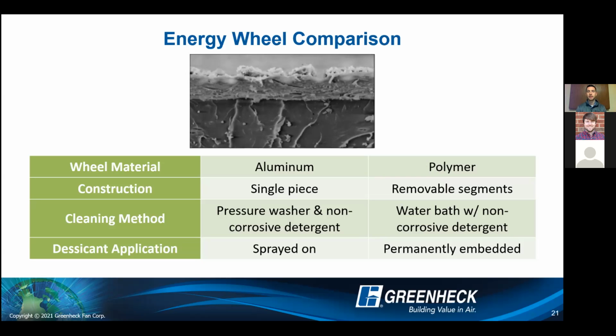So with that aluminum wheel, I talked about the molecular sieve desiccant doing that latent transfer. That is a sprayed on application. So when you're spraying on that desiccant, if you're cleaning it and pressure washing it and rubbing it off over the course of that lifetime, you might flake off that desiccant, which means you'll lose that latent or that humidity transfer. With the polymer wheel, they actually have a permanently embedded desiccant. So you can see that picture right there. What Air Exchange does is they take those polymer strips, they apply a chemical solvent to soften that strip down, and then they provide that silica gel desiccant. Once that's applied, that polymer dries, and then it actually embeds that silica gel desiccant into that polymer material as shown in that picture. So when you're cleaning it over the lifetime of that wheel, you see a significant reduction in the loss of latent energy transfer, or that risk of the desiccant flaking off.